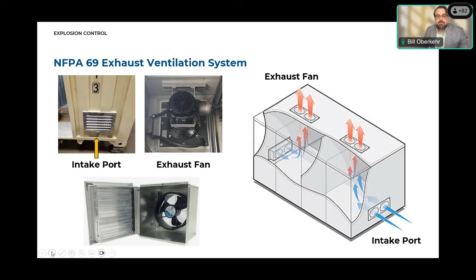Explosion control under the NFPA 855 standard, which again is the parent standard, is not always required. We have some exceptions here. If the UL 9540A large scale fire test shows that there is no flammable gas at the cell level or the module level, then we don't need that, obviously, because again, data driven decision making, data driven requirements. If you can show documentation that the system cannot possibly generate more than 25% of the lower flammable limit of the gas under thermal runaway conditions, that's also going to get you an exception. I'm not going to read through all of these for the sake of time. They are in this presentation, and more importantly, they are in section 1207 of the fire code. Next slide, please.